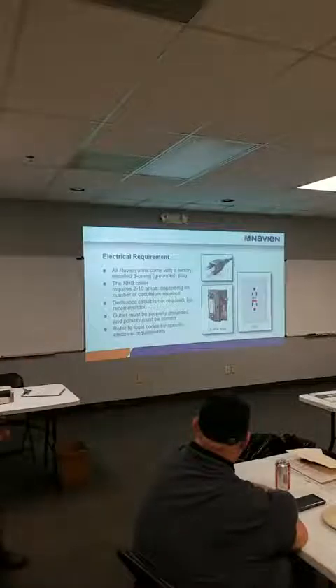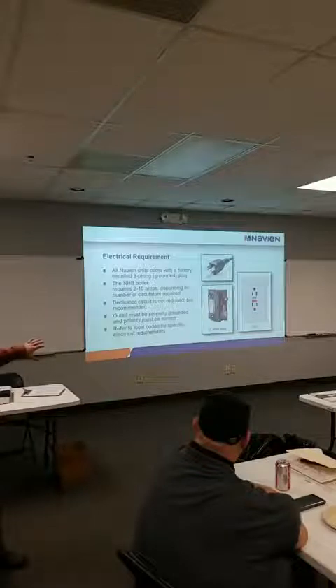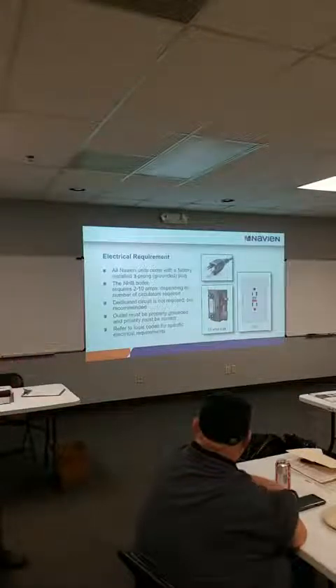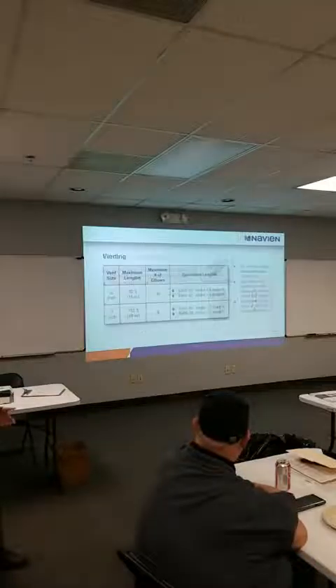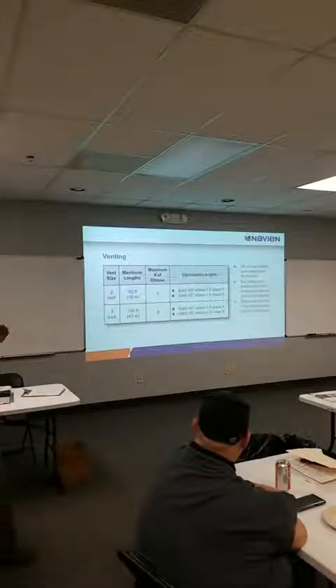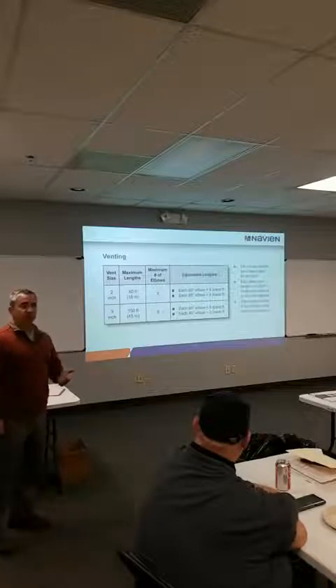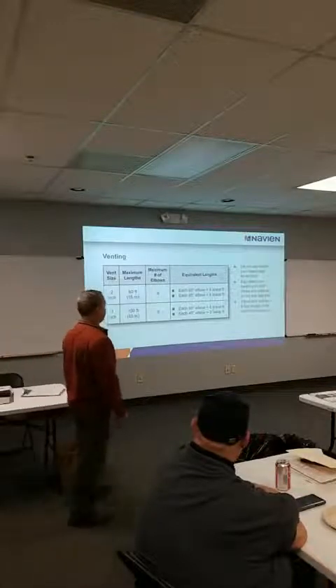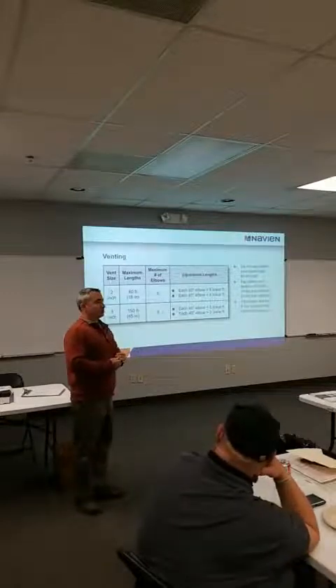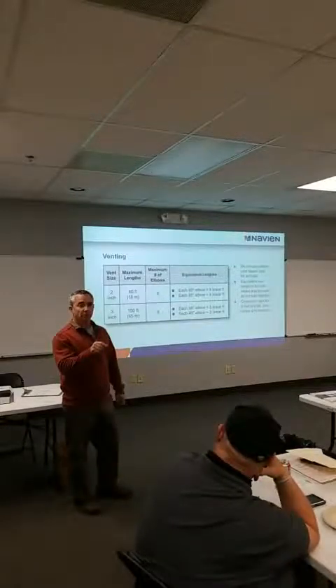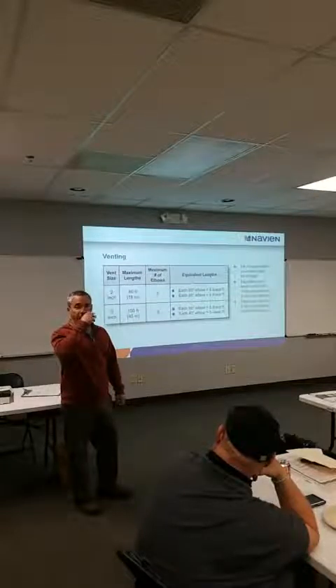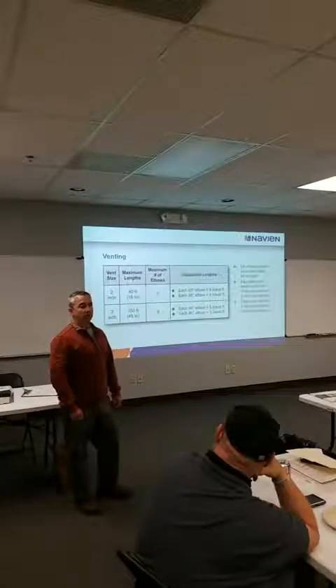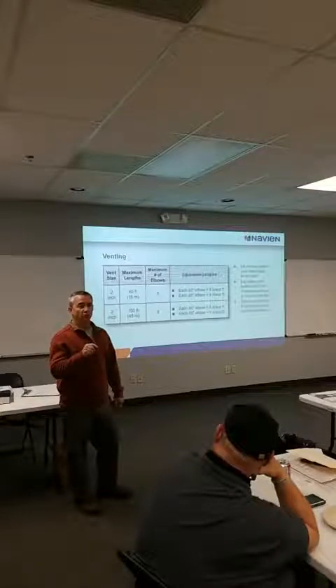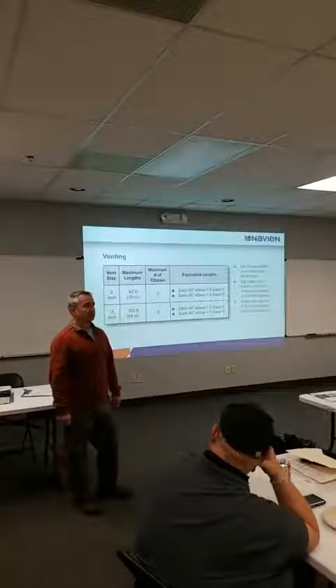All of our units plug right into the wall. 15 amp breaker, minimum. We show pictures of GFI because I think we have to, but we're not big fans of GFI, with the computer board that's in there. But I know some places you have to use them. How sensitive are the electronics on that machine? Pretty sensitive. It's a computer. So I carry around a little polarity and ground checker. If I ever go to a job, I check the electricity, because we do flame rectification to ground. So if it's not grounding properly, you're going to have flame out issues.